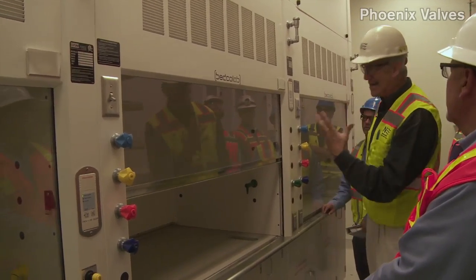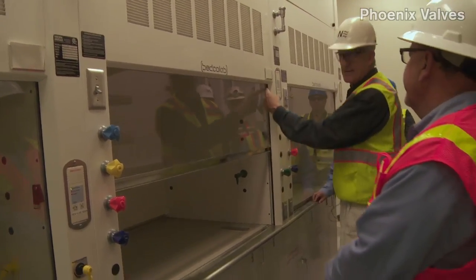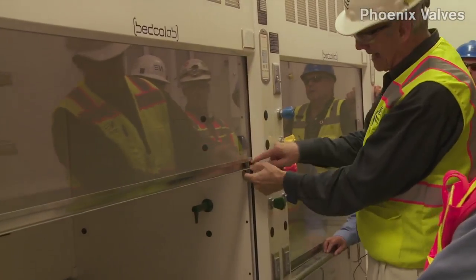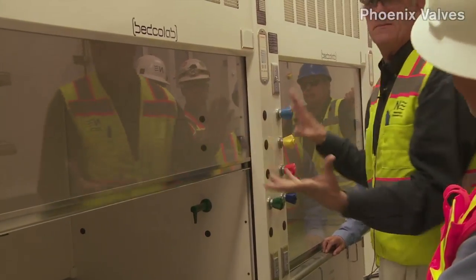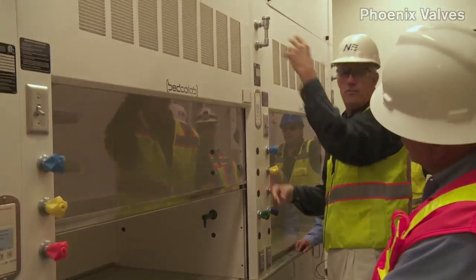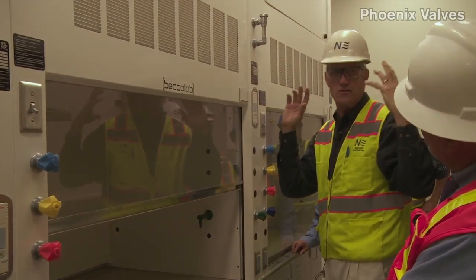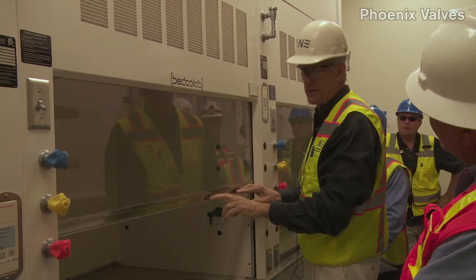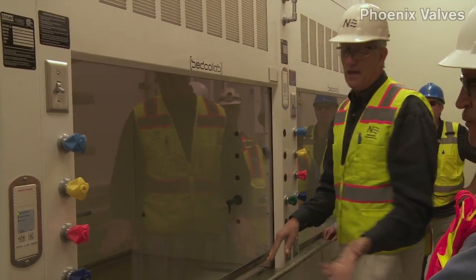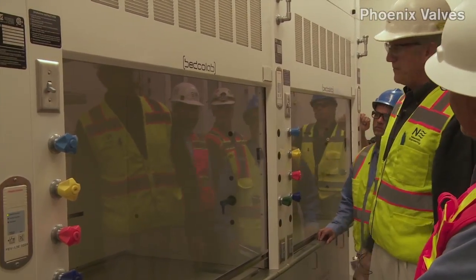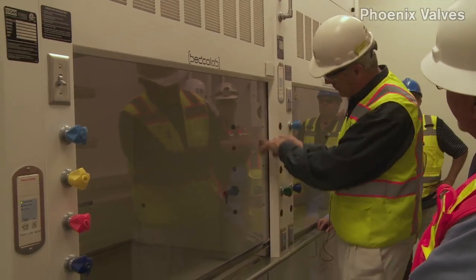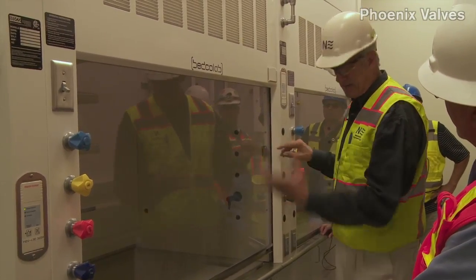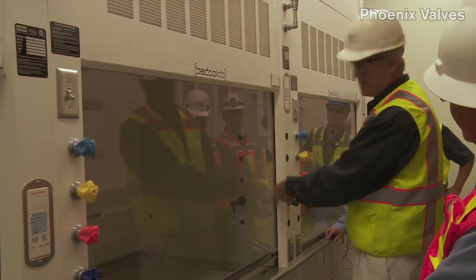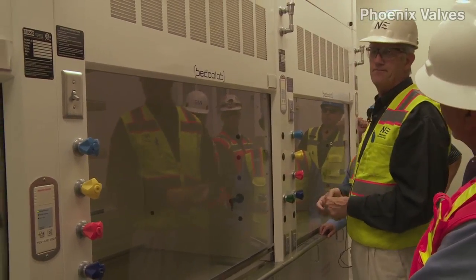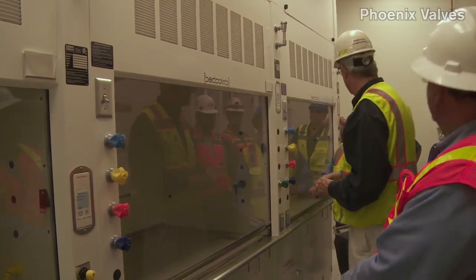An alternative thing is this sash sensor is attached to this sash. If that somehow comes disconnected, it'll retract all the way back in and it'll perceive the sash is too far open. That's a third possibility. So if you come out and you have a slow beep, make sure that button's not pushed. Make sure the sash is below the sash stop. If neither of those stops the slow beep, probably this cable came disconnected. Make sense?